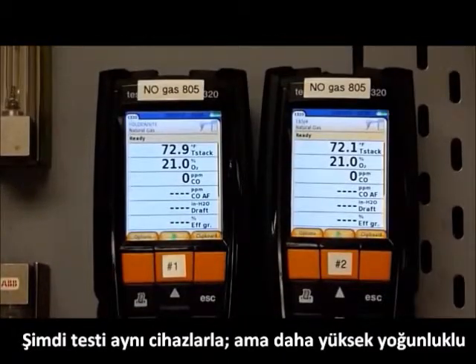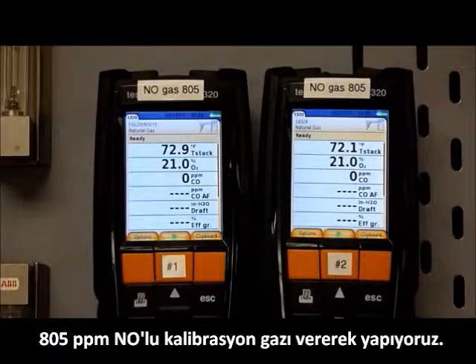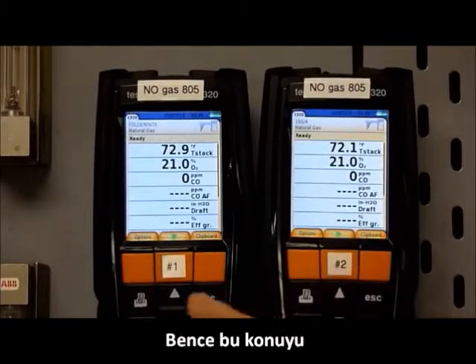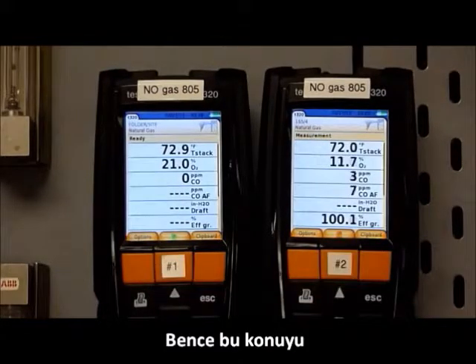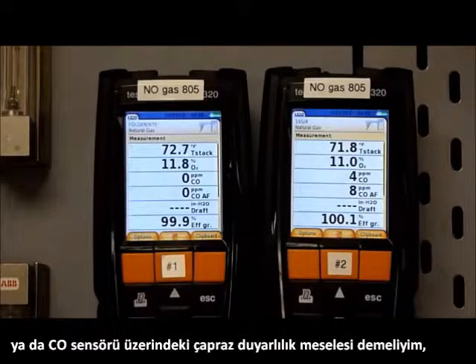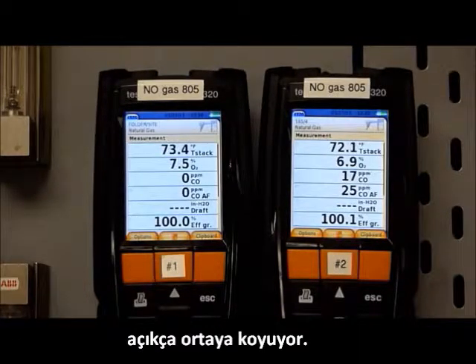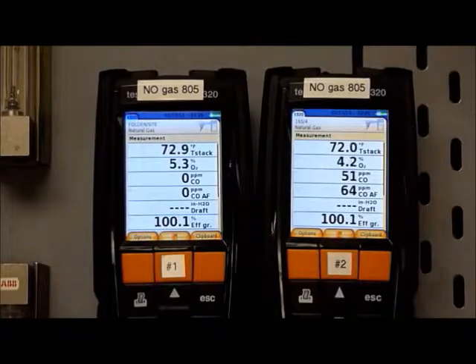Okay, now we're going to retest the same analyzers but using a higher concentration NO calibration gas at 805 ppm. I think this demonstrates the matter, or should I say the phenomenon of cross sensitivity on the CO sensor pretty obviously.